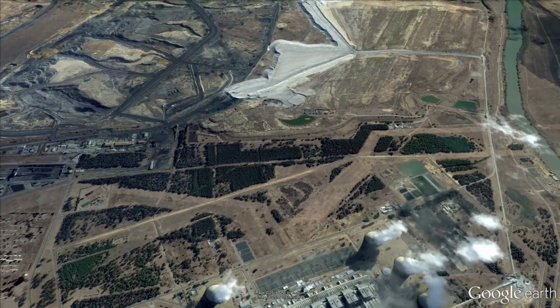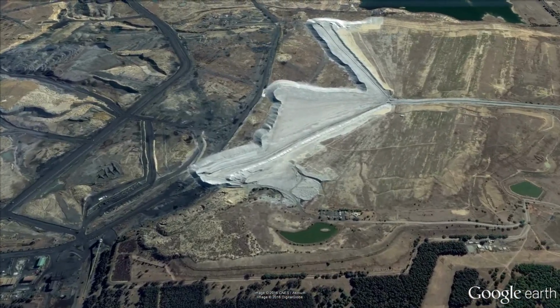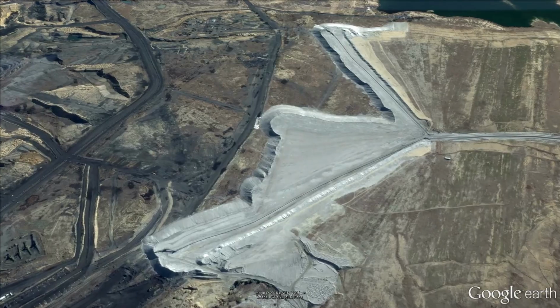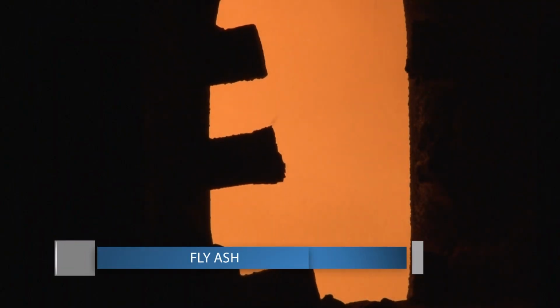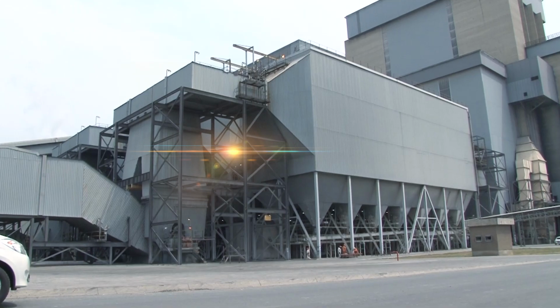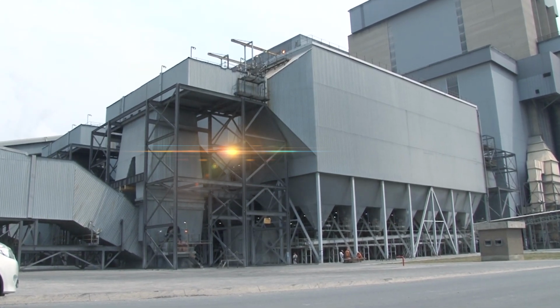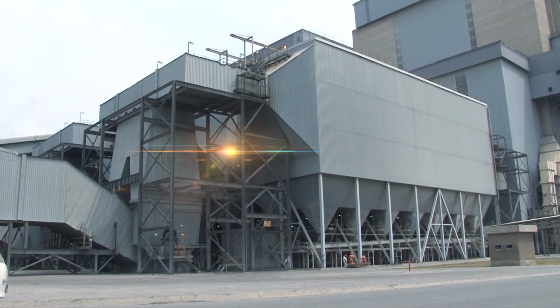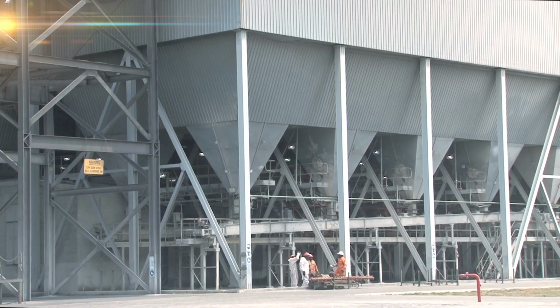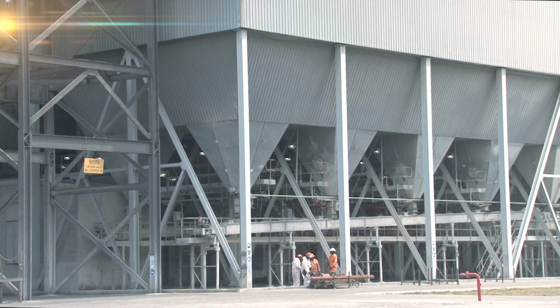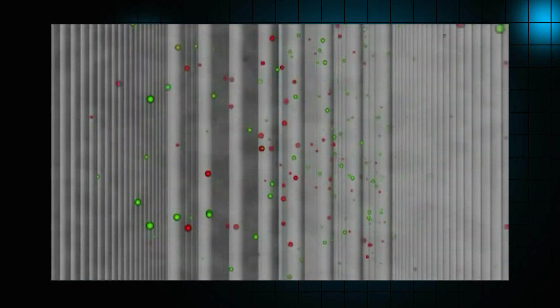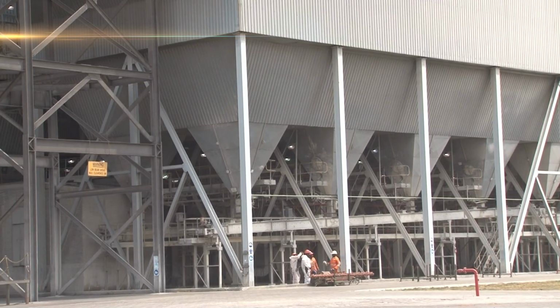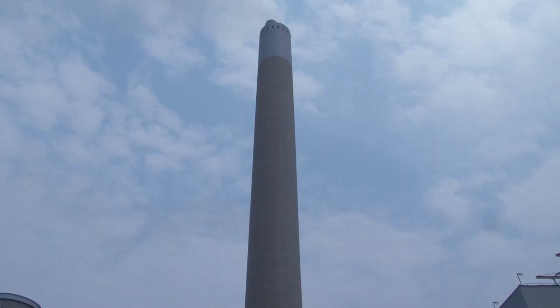The ash is removed from the boiler and stored in large ash piles. Fly ash is the very light ash that flies around in the air when there's a fire. Electrostatic precipitators have been installed to remove 99% of the fly ash in the air that results from coal being burnt in the power station. They use electrically charged plates to attract the ash, which is fed out of the bottom of the plant. The exhaust gases are vented from the top of the chimneys.